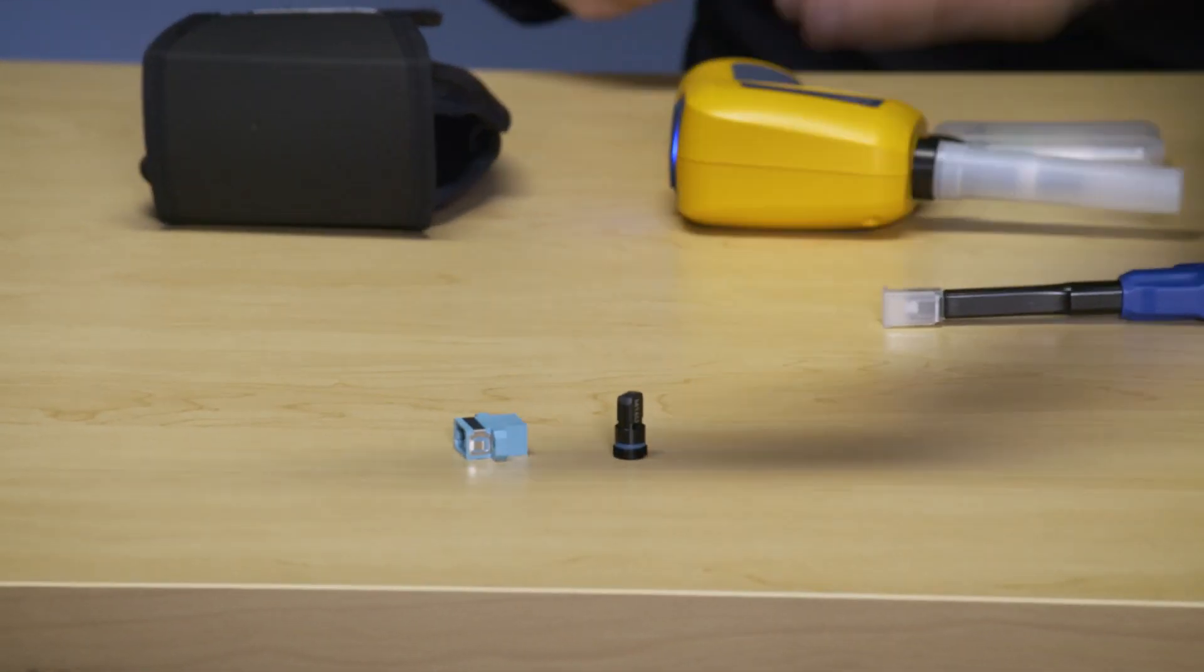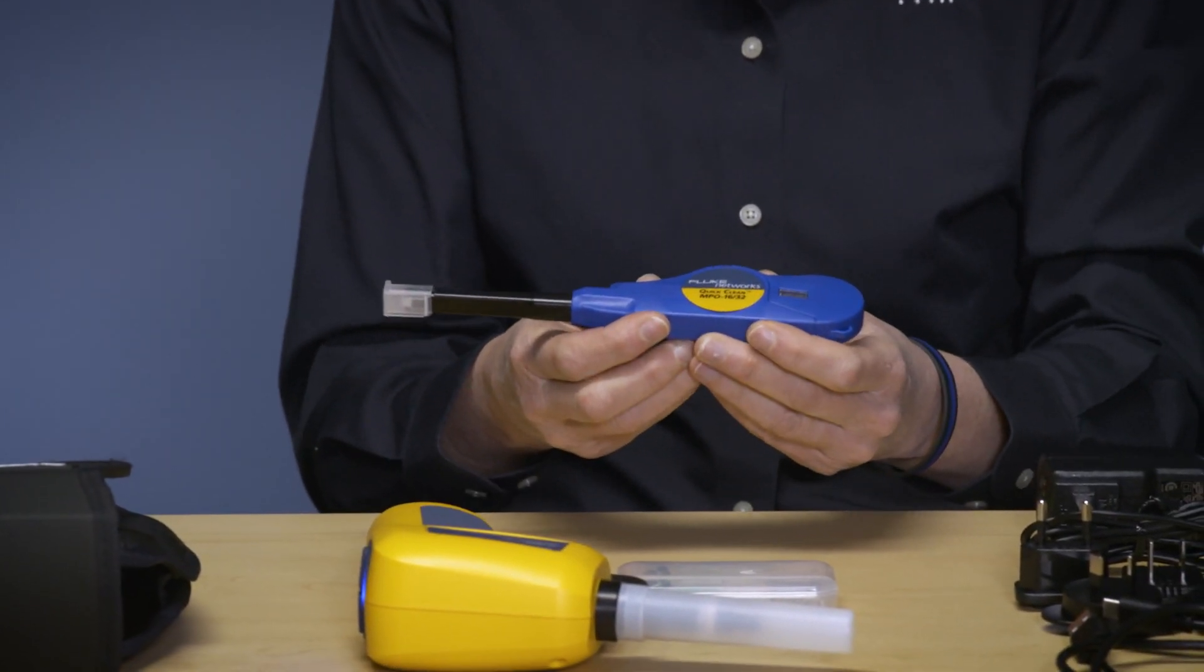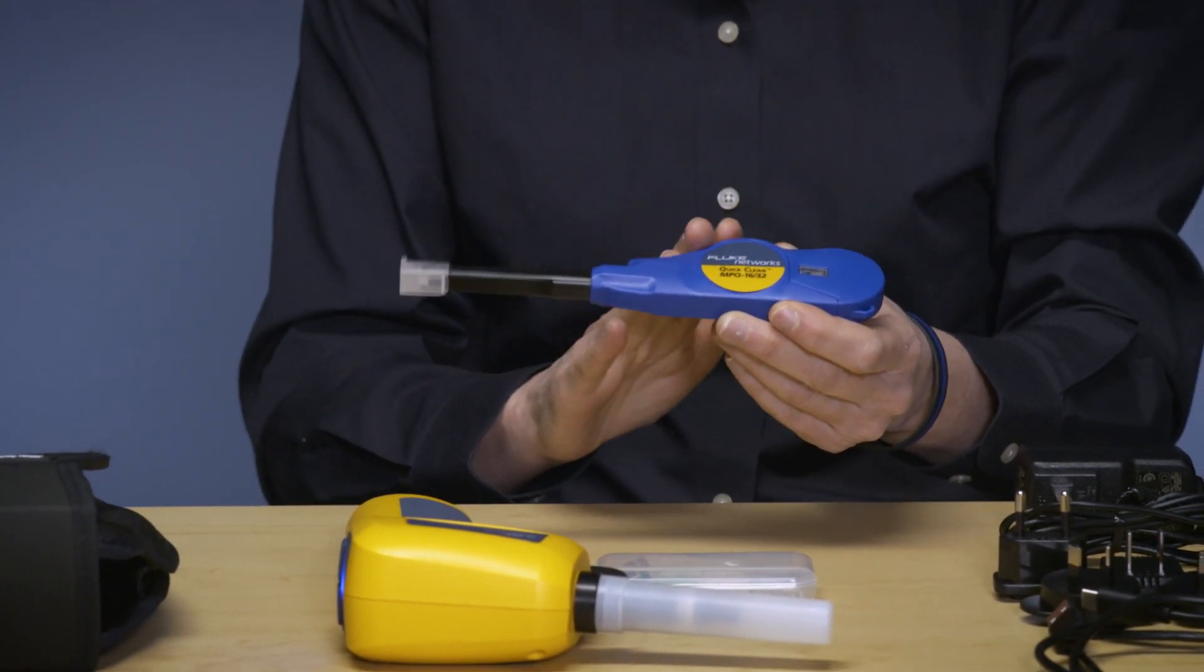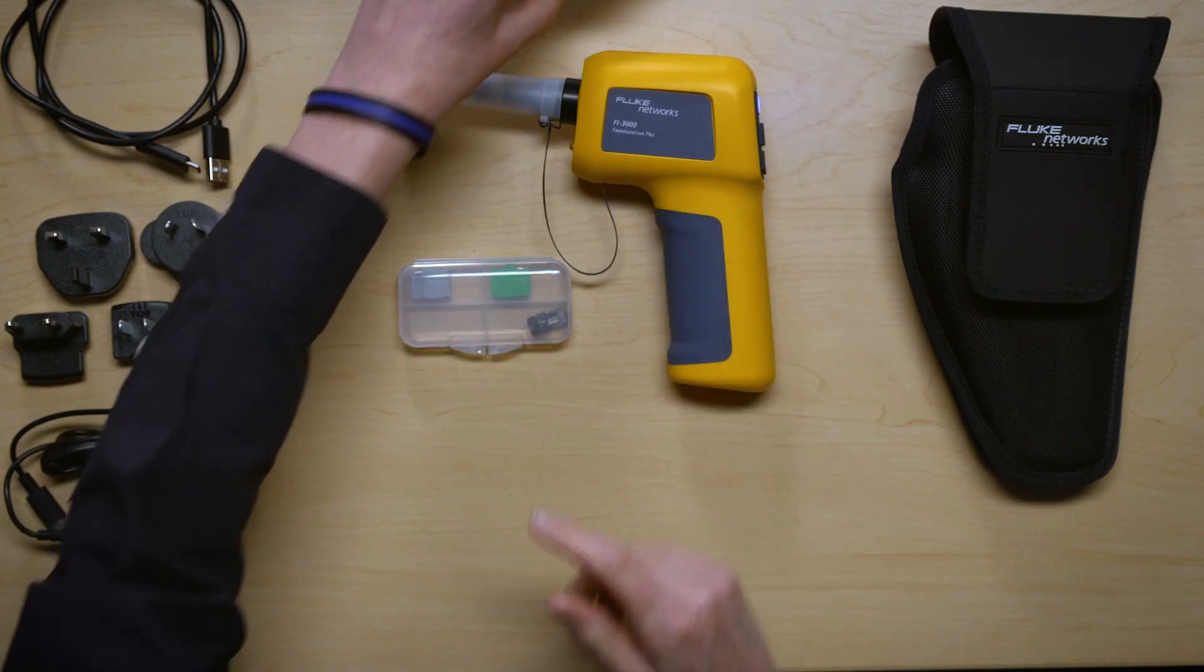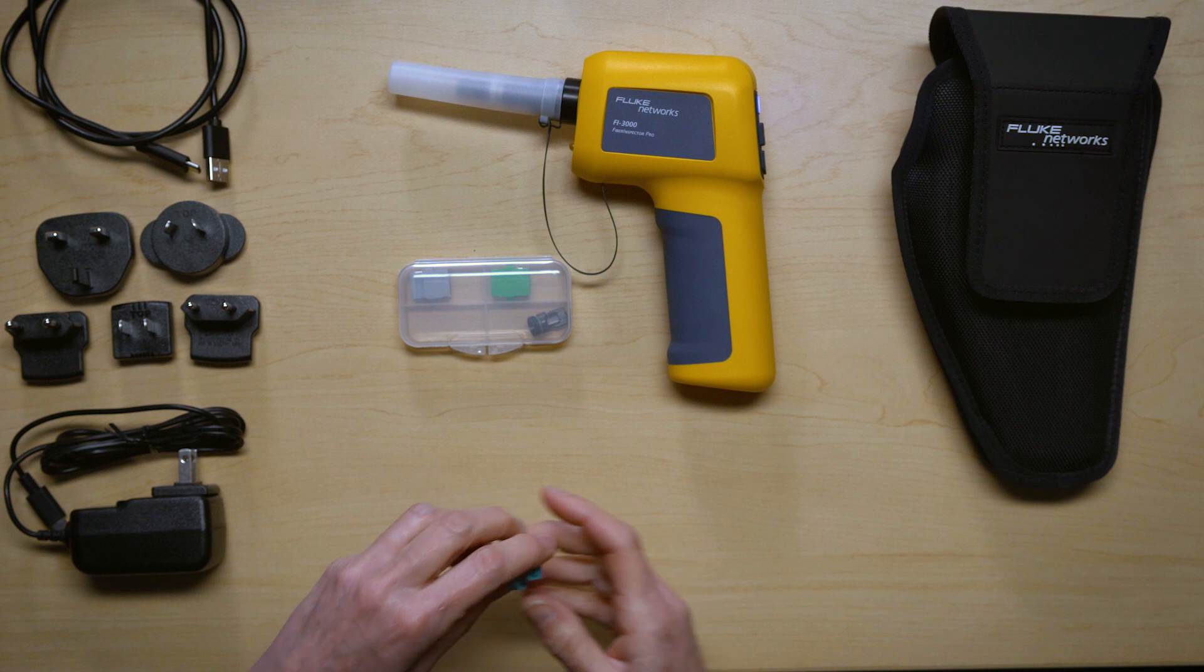I have a second one. This one is for 1632s. So if I have a 1x16 or a 2x16 giving me 32 fibers this is what I'm going to use.